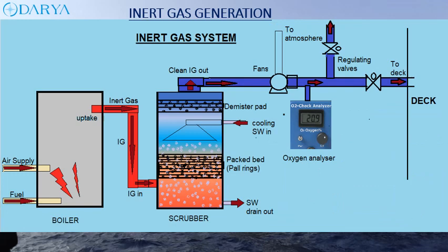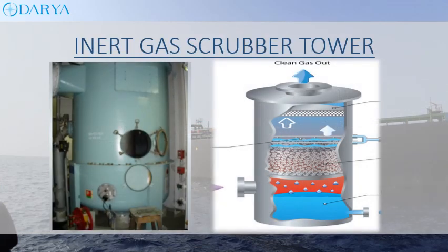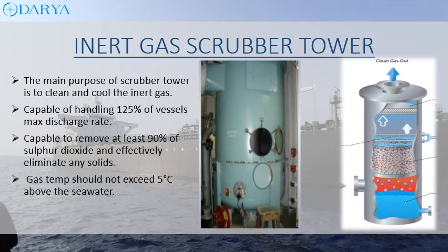The main purpose of the scrubber tower is to clean and cool the inert gas. It is capable of handling 125% of the vessel's maximum discharge rate, removing at least 90% of sulfur dioxide, and effectively eliminating any solids. Gas temperature should not exceed 5 degrees Celsius above the sea water temperature.